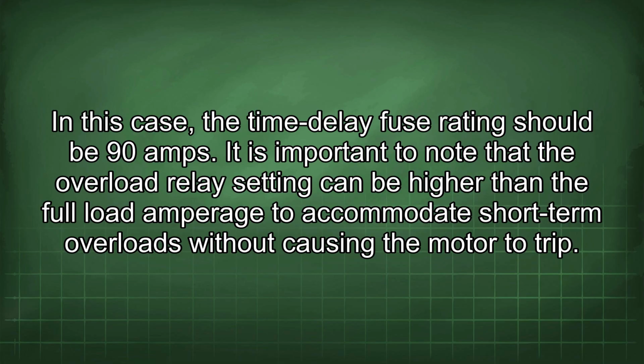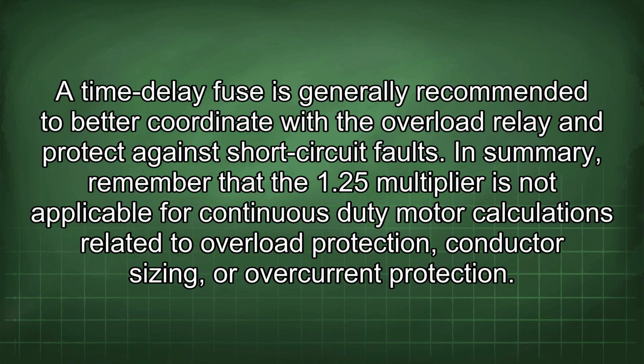It is important to note that the overload relay setting can be higher than the full load amperage to accommodate short-term overloads without causing the motor to trip. A time delay fuse is generally recommended to better coordinate with the overload relay and protect against short-circuit faults.